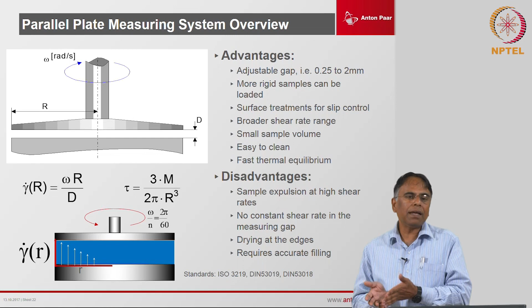Let us say we start with 1 mm gap. Now as the temperature is increasing, the expansion is happening, so the gap is actually becoming smaller. We can already track that by knowing the material. We know the coefficient of expansion of that material, and based on that we can know how much the gap is getting lowered. That is used for calculations, and that correction is made very easily. That correction cannot be done with a cone and plate.